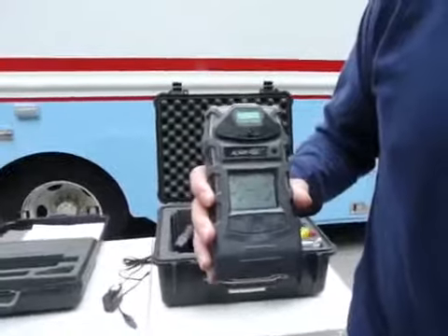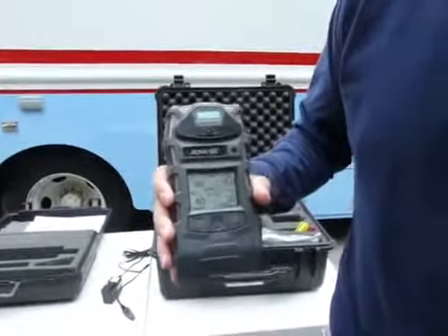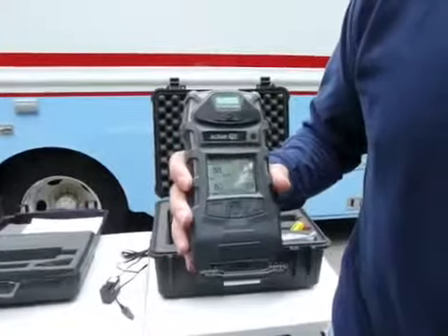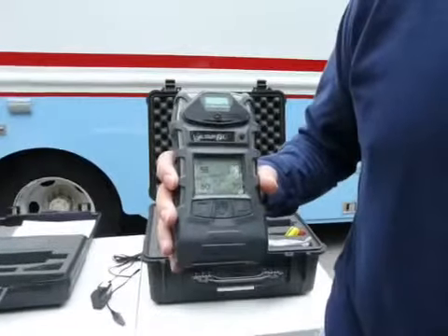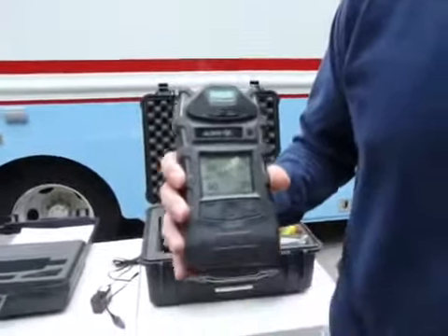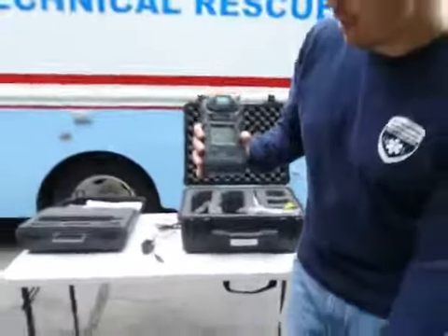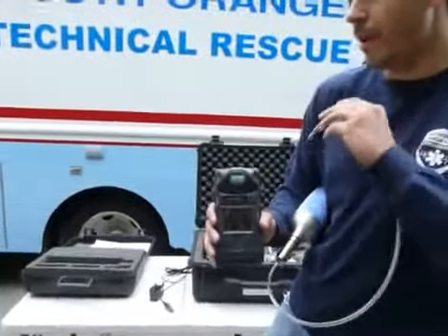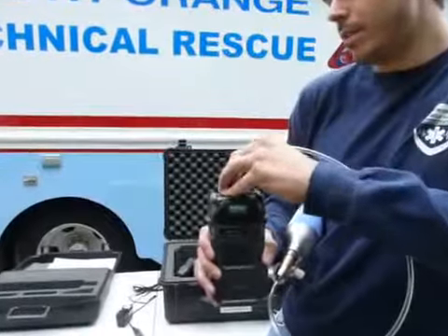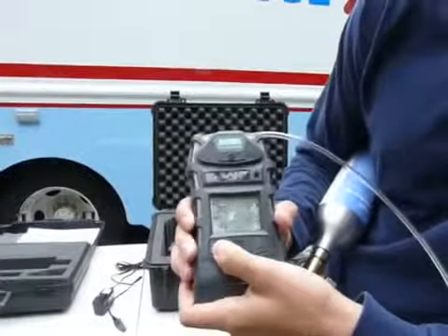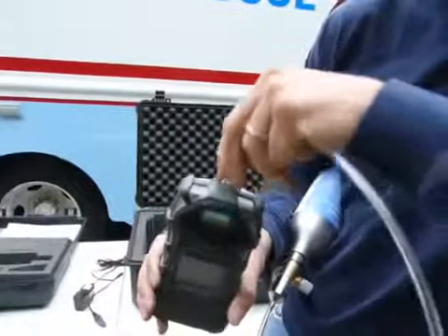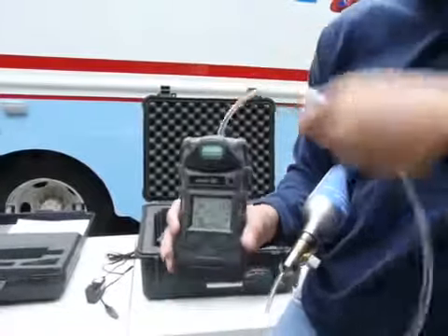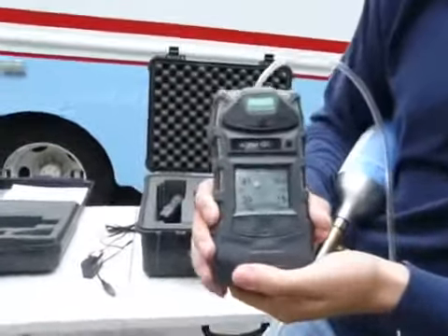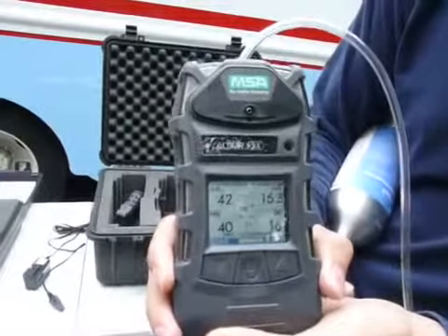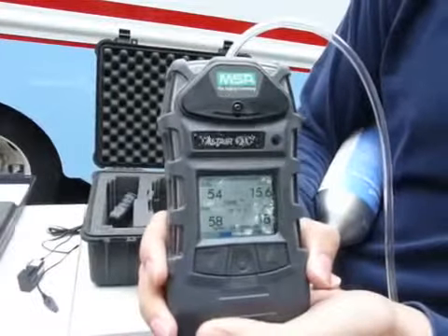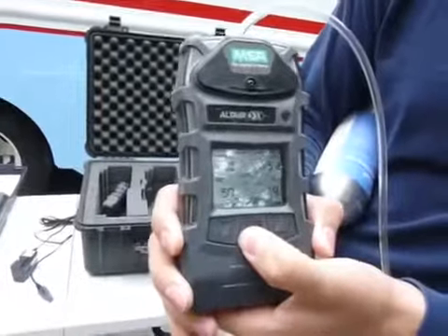We've successfully zeroed out all the sensors, and the next step now is going to be to expose the unit to the calibration gas. And each of these values here corresponds to the known concentration of the gases within the calibration gas. So now I'm going to turn my calibration gas unit back on, let it flow freely, all the way open, connect it to the back of our unit, and then hit yes to say that we want to span the calibration. This is basically going to span or help calibrate each of these sensors so that they have a known quantity or a known concentration to go off of. And this is going to take about 1 extra minute.